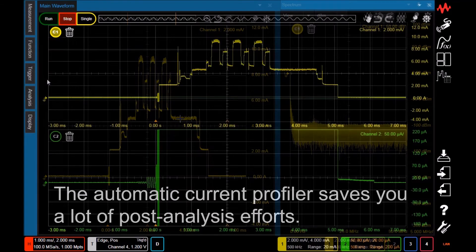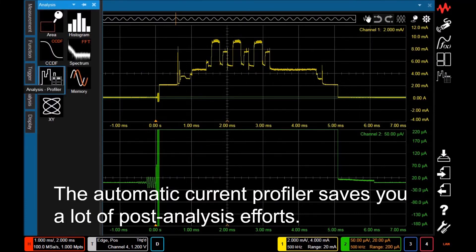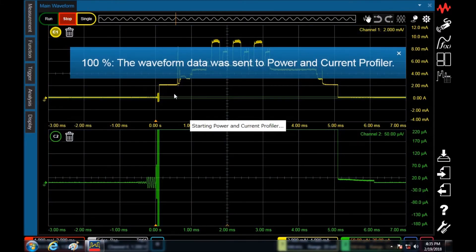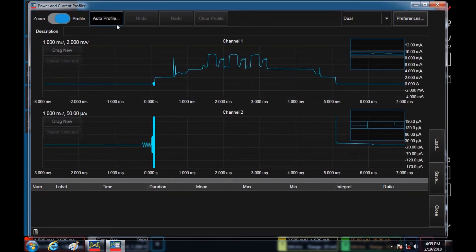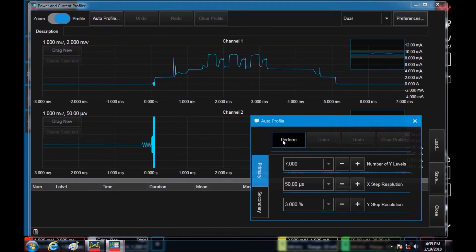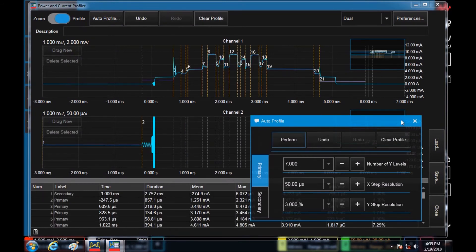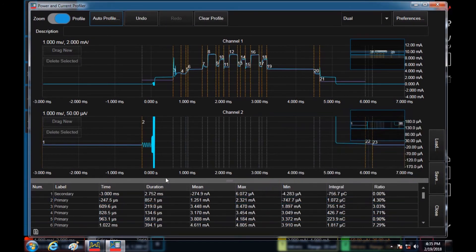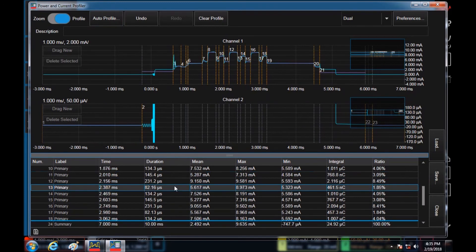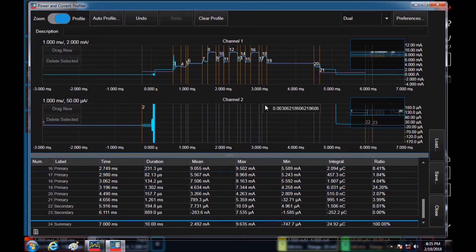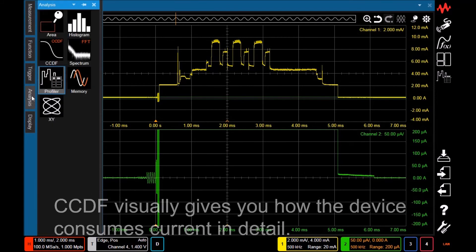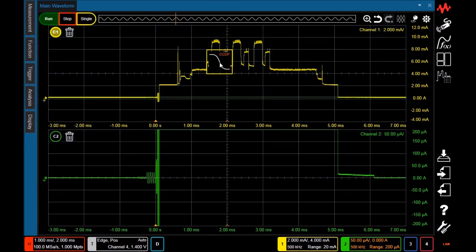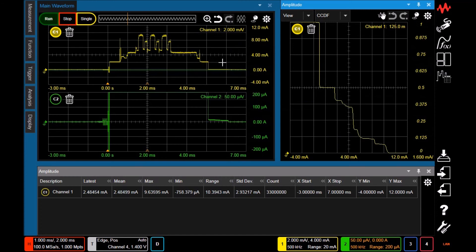The automatic power and current profiler is a time saver. By dragging and dropping the icon from the analysis palette, a new window duplicating the measured waveform appears. The automatic profiler automatically detects waveform transitions and indicates these transitions on the waveform. The bottom table shows key measurement values such as averaged current or charge amount for each segment. A variety of statistical analyses is available. The CCDF function shows you how the current profile is built and is very helpful for current consumption reduction.